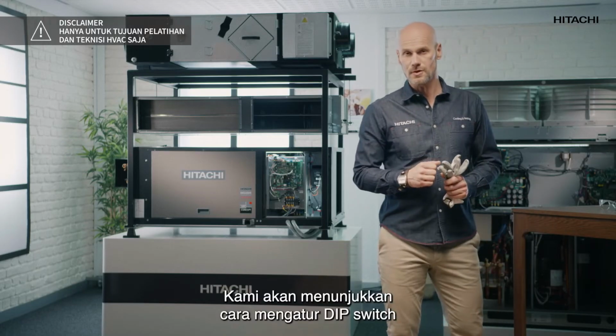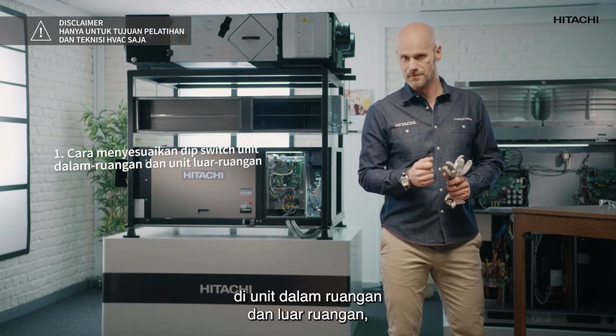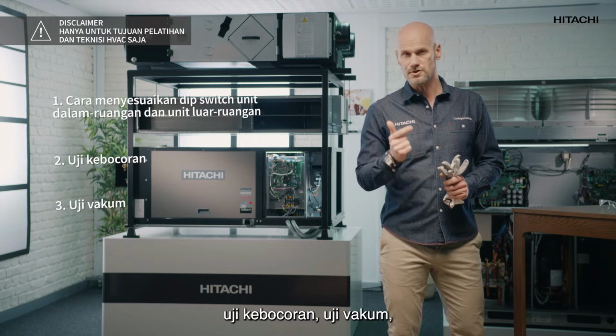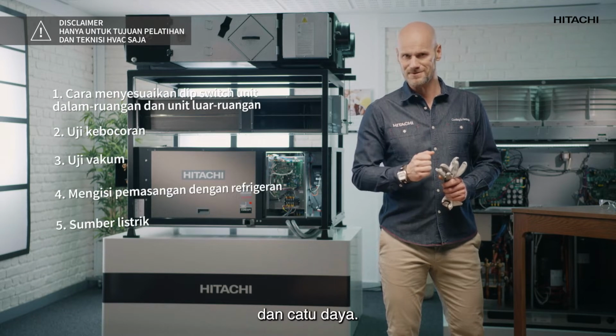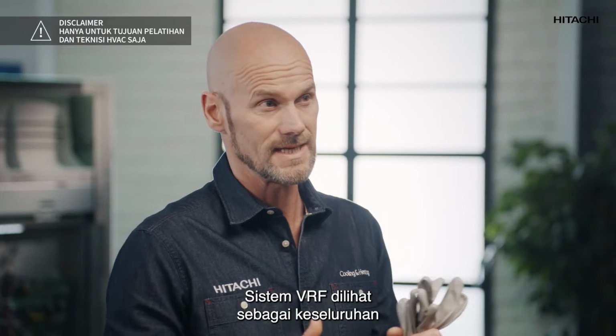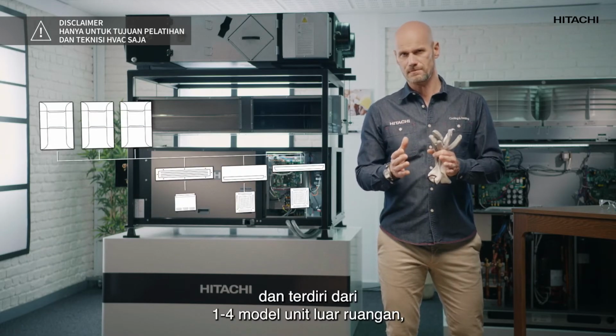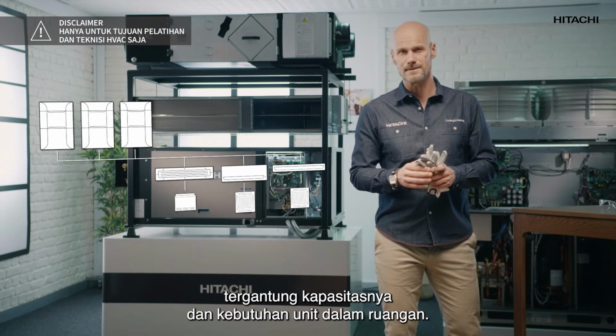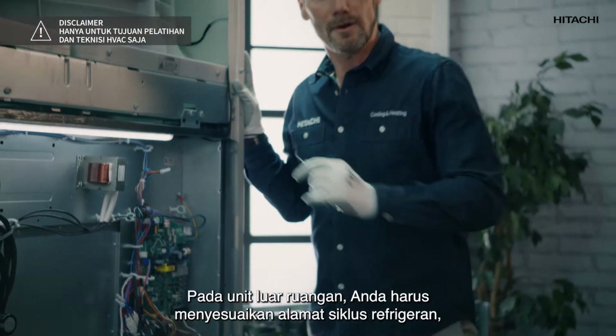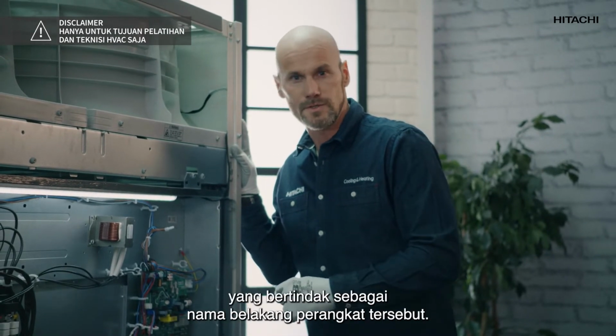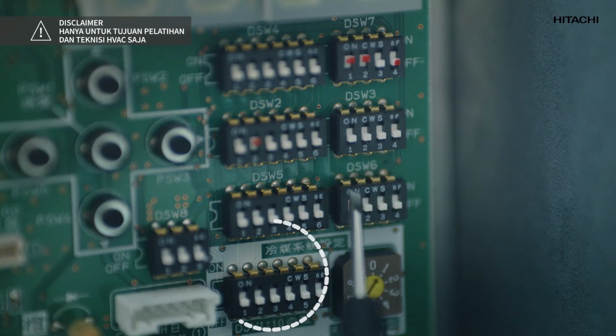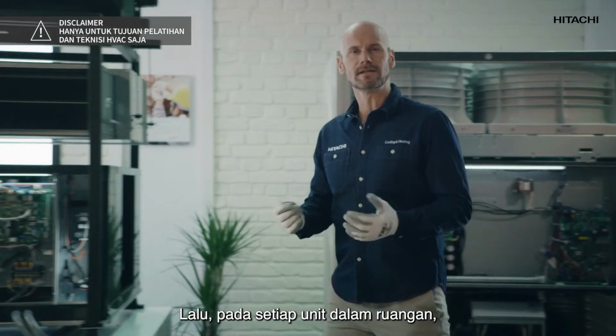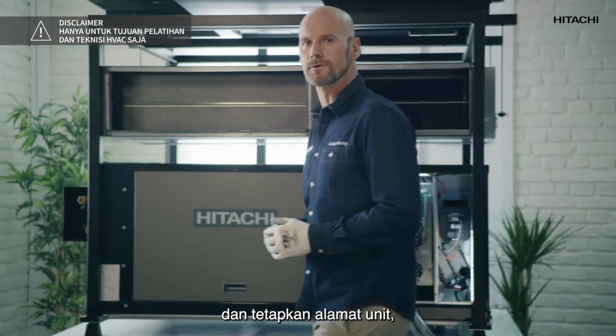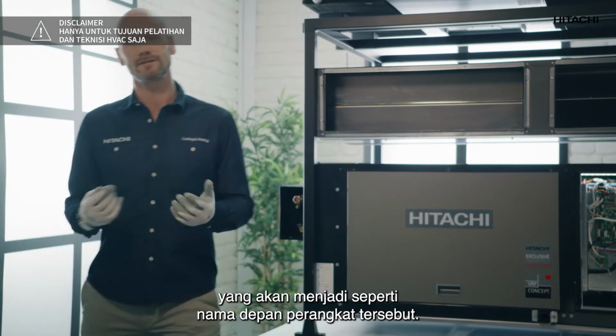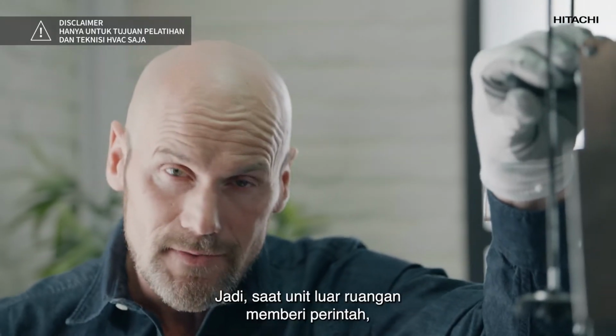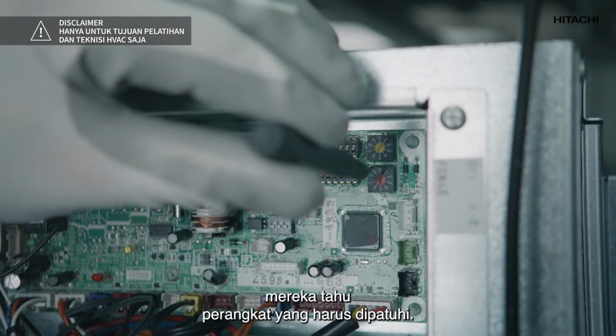In this video, we are going to show you how to adjust the dip switch for the indoor unit and the outdoor unit, a leak test, a vacuum test, charging this installation with refrigerant and the power supply. As you know, a VRF system has to be seen as a whole, and it consists of 1 to 4 outdoor unit models depending on the capacity and the necessary indoor units. In the outdoor units, you have to adjust the refrigerant cycle address, which is something like the equipment surname. And then for each indoor unit, you have to adjust the refrigerant cycle, and you also have to set the address of the unit, which would be like the first name of the equipment. So that when the outdoor unit gives them an order, they know who they have to obey.